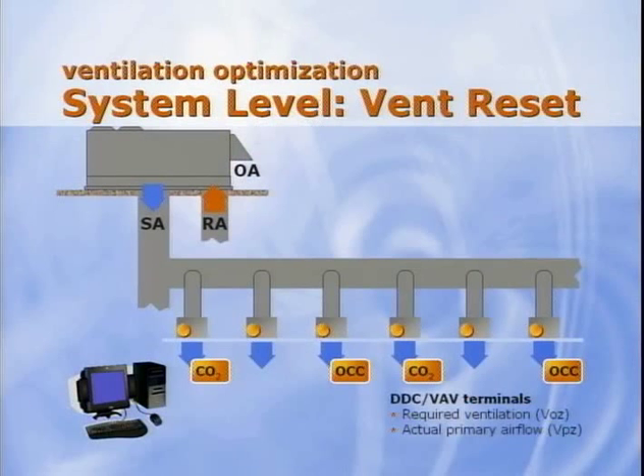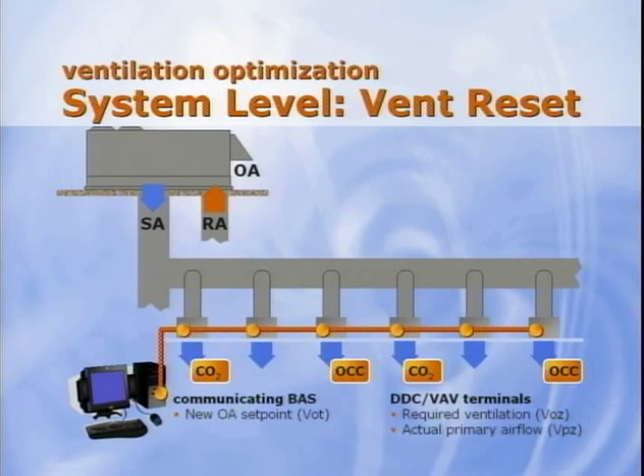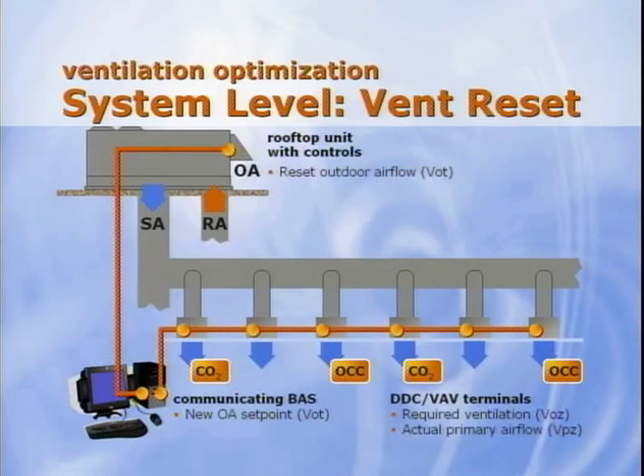In addition to resetting the zone's ventilation requirement, the controller on each VAV terminal continuously monitors primary airflow being delivered to the zone. Then, the BAS periodically gathers this data from all the VAV terminals and solves the ventilation reset equations to determine how much outdoor air must be brought in at the rooftop unit to satisfy all the zones served. Finally, the BAS sends this calculated outdoor airflow set point to the rooftop unit, which modulates a flow measuring outdoor air damper to maintain this new set point.